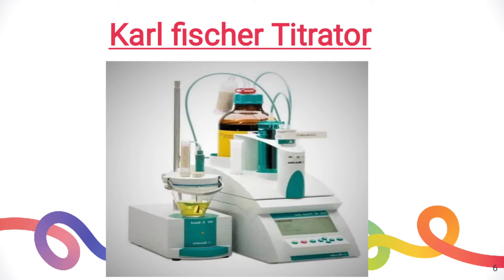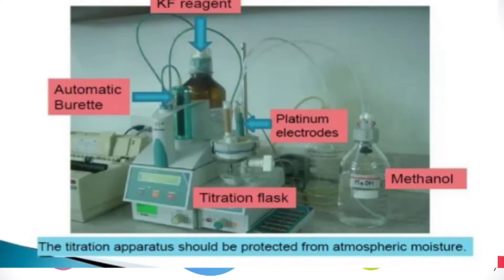This is how the Karl Fischer titrator looks like. The different parts of the titrator are shown here. The amber glass bottle that we can see is used to fill KF reagent, as KF reagent is light sensitive and is therefore stored in an amber colored bottle. There is also an automatic burette, titration flask, and a double platinum electrode used for the purpose of accuracy, along with a bottle of methanol.